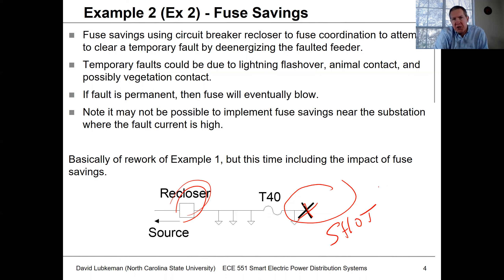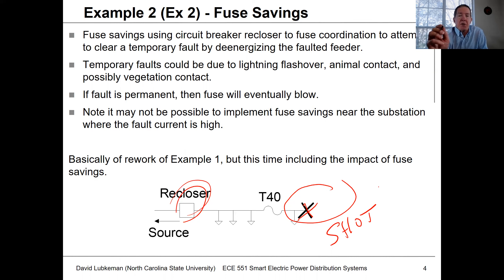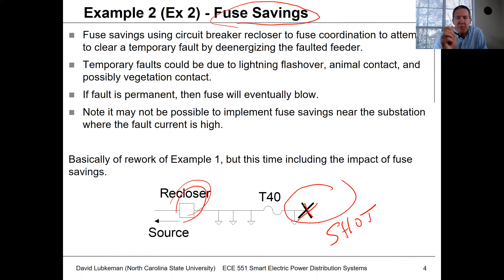The utility might use one, two, or three shots. After that, the recloser will switch curves — it'll go to a slower curve and force that fuse to blow. So if it's temporary, the recloser clears the fault. If it's permanent, the fuse ends up blowing. This concept is what's referred to as fuse savings.